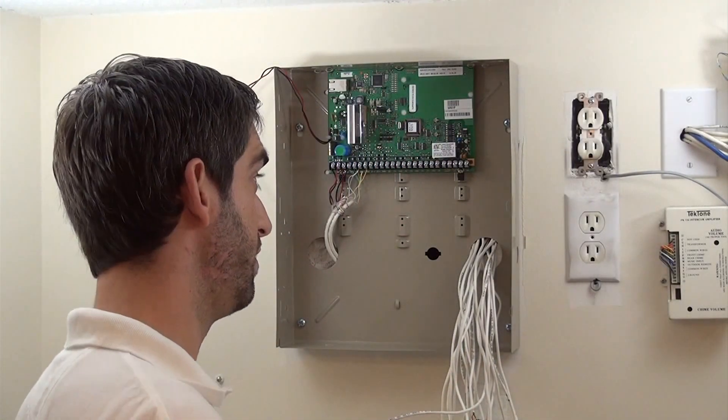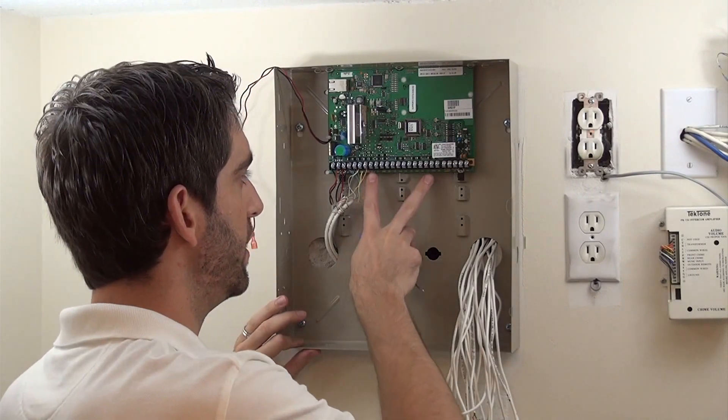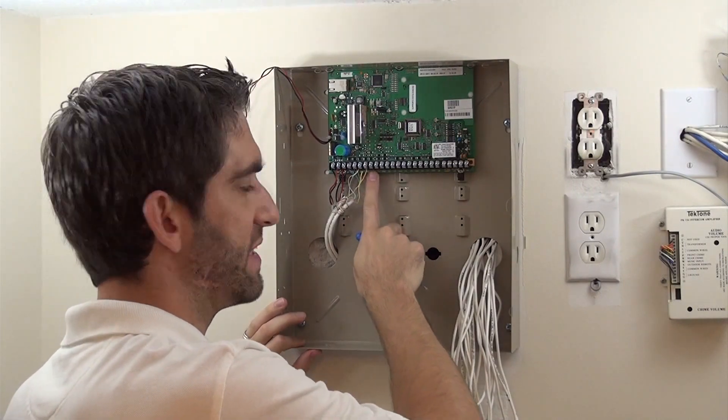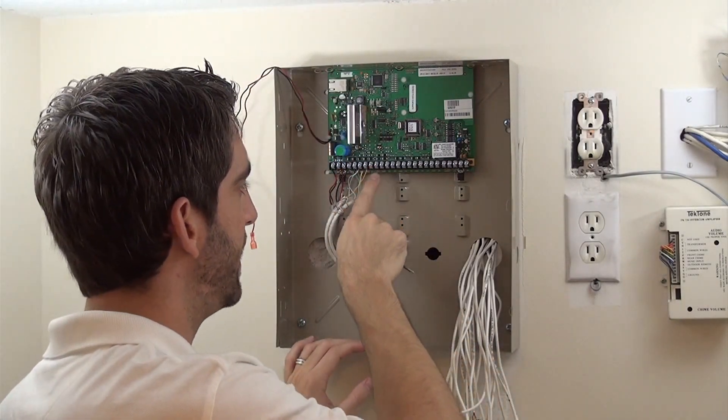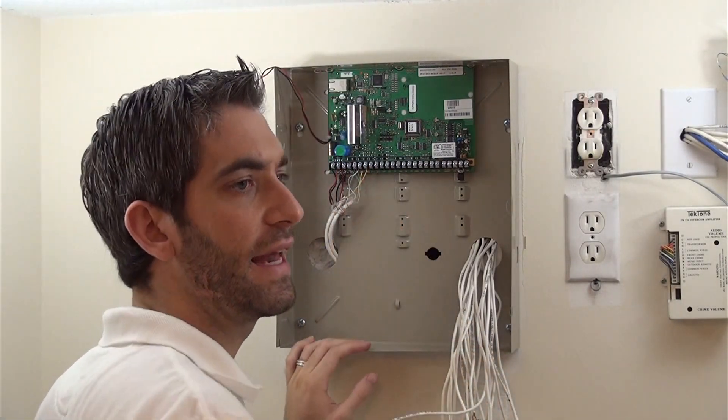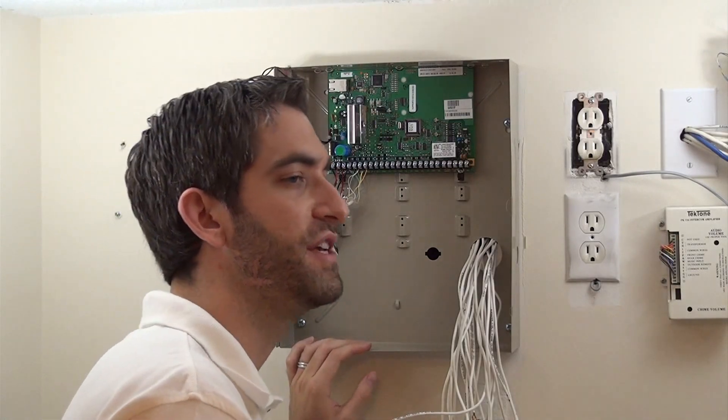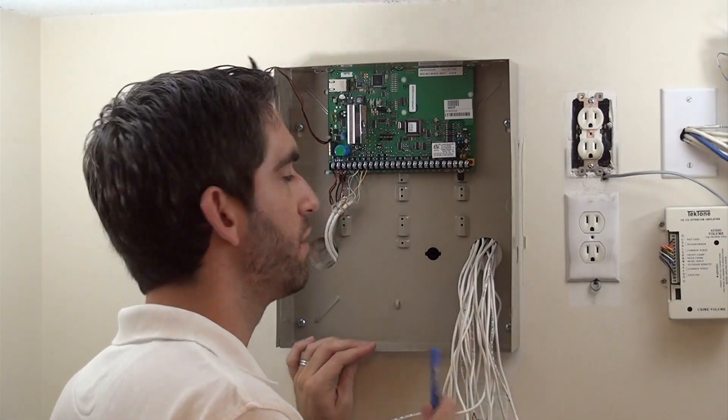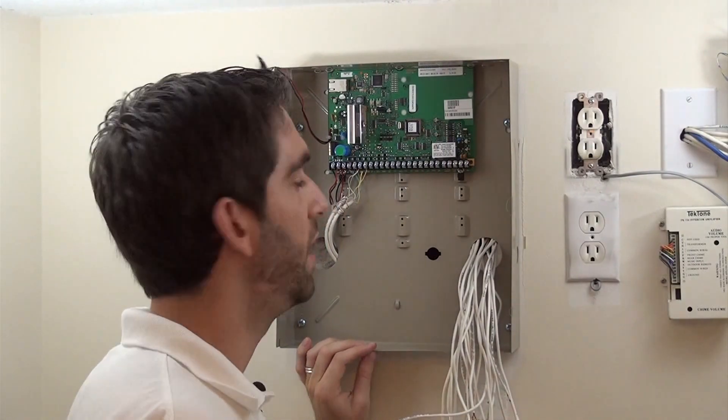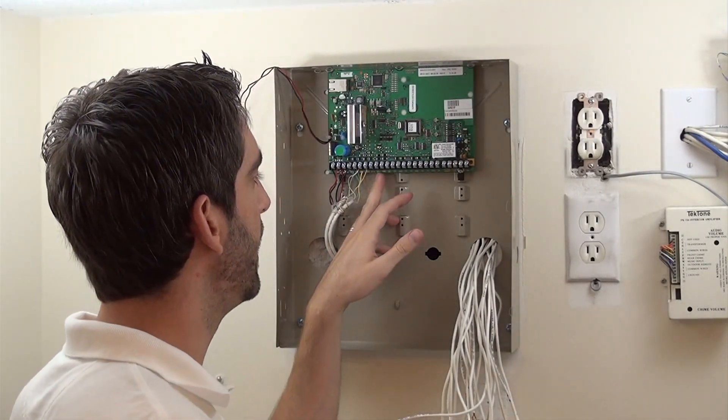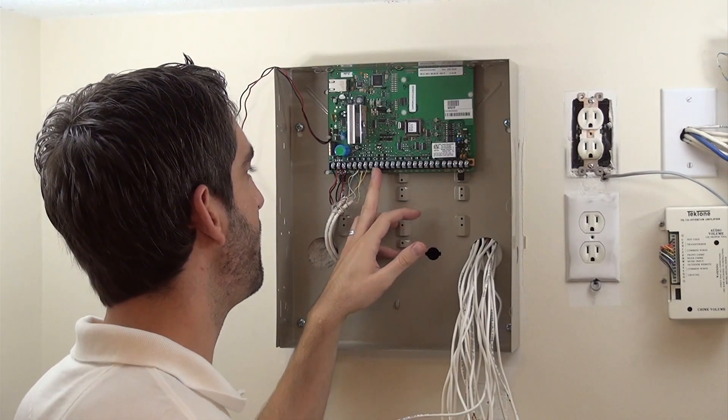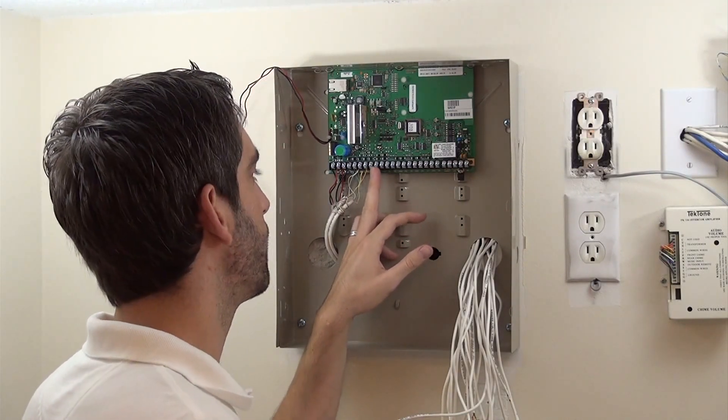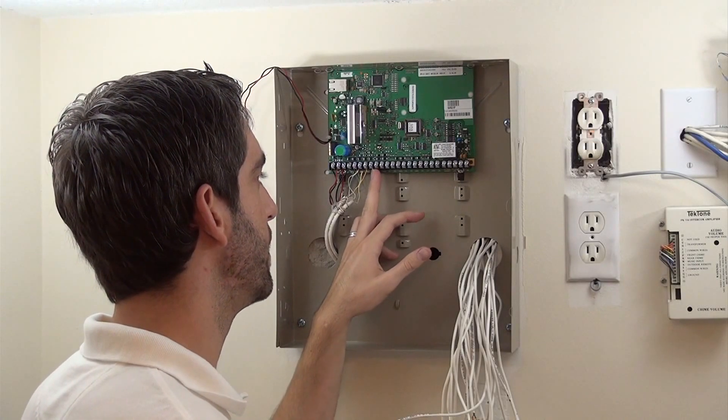The VISTA-21IP comes programmed with zones one through eight enabled. Zone one is set up as a fire zone by default. Two wire smoke detectors attached to this first terminal get an auto power reset when you disarm the system. So if you are going to have wired smokes, you should always use terminals Z1 plus and Z1 negative. For us, we don't have any smoke detectors tied into this system. So we're going to use that as a simple door window zone.